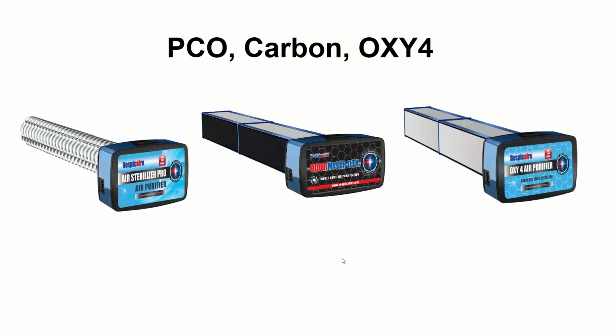You're going to want to put it in the air handler because the dimensions of the air handler are wider than the dimensions of the duct. Therefore, the velocity is slower, which is going to help me. Plus, I want it to mainly shine on the coil because that's where it's going to do the most work. Will it kill the germs in the air that go by it? Sure, it'll work on killing those germs too, but that's not its main job. Its main job is killing germs on the coil. So definitely on the coil.